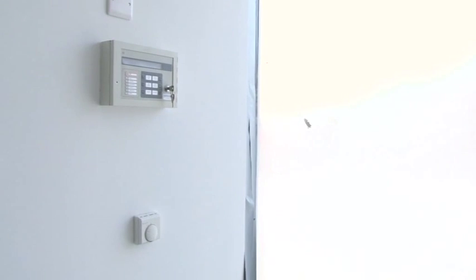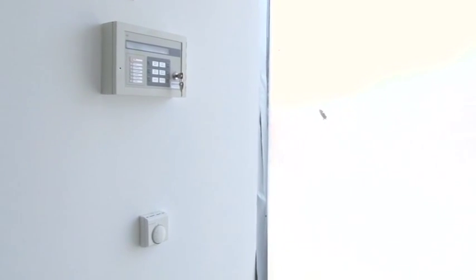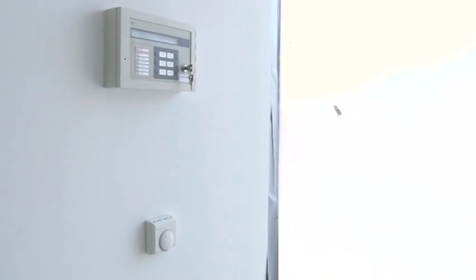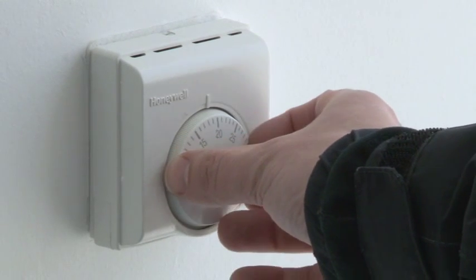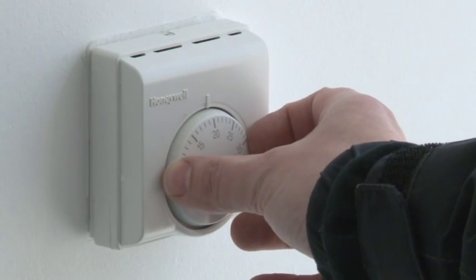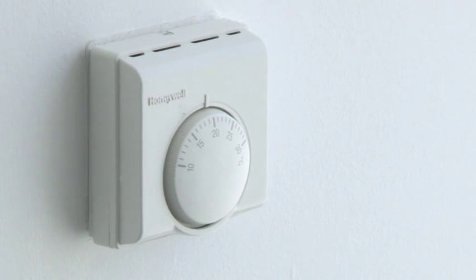And then there's a temperature controller on the wall behind us, basically. So what it's detecting there is the temperature in this area. So if it's already warm, then you wouldn't get that blast of heat, but obviously when those doors are open in the winter, then it'd be cooled down, and that's when it'd be on to provide heat into the area and to provide that curtain of air over the door to stop heat going back out of the building.